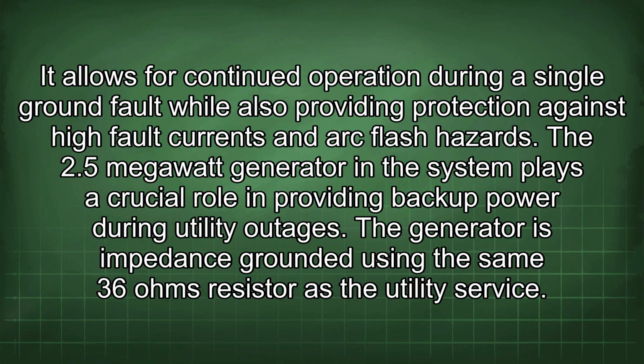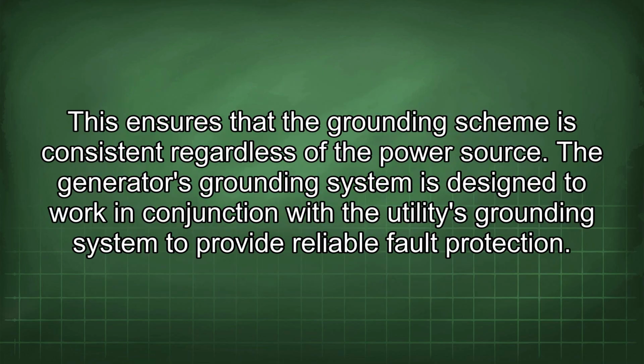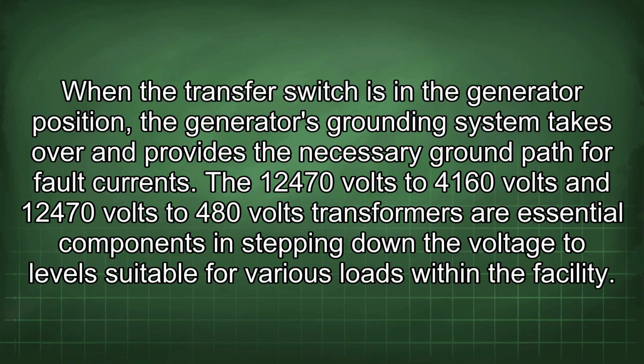The 2.5 megawatt generator in the system plays a crucial role in providing backup power during utility outages. The generator is impedance grounded using the same 36 ohms resistor as the utility service. This ensures that the grounding scheme is consistent regardless of the power source. The generator's grounding system is designed to work in conjunction with the utility's grounding system to provide reliable fault protection. When the transfer switch is in the generator position, the generator's grounding system takes over and provides the necessary ground path for fault currents.